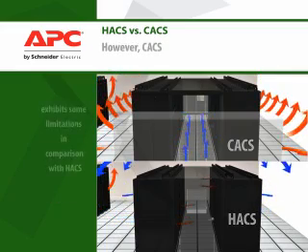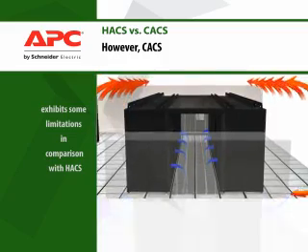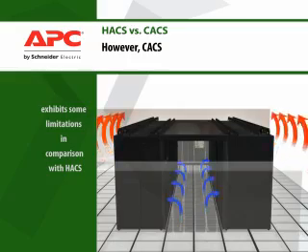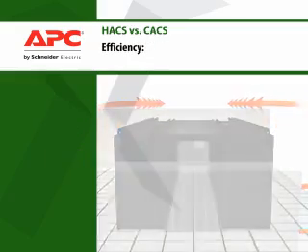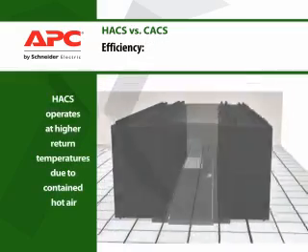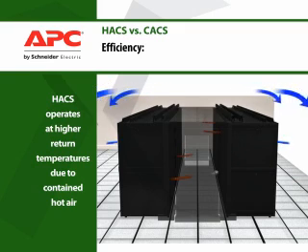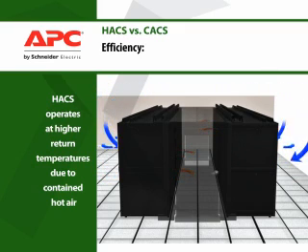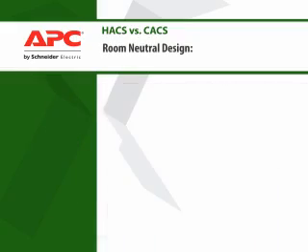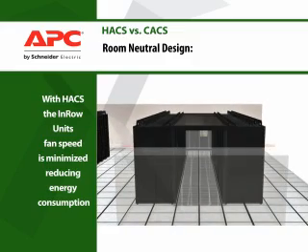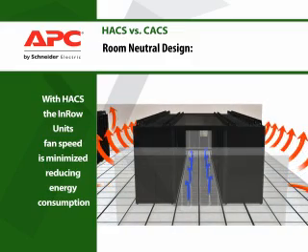While both the hot aisle and cold aisle systems help solve today's data center challenges, the cold aisle containment exhibits some limitations in comparison with the hot aisle system. With the hot air contained, the in-row cooling units are able to capture all of the heat from the IT equipment. Mixing from the room is also eliminated, which increases the return temperature, increasing cooling capacity and efficiency of the in-row cooling units. With mixing eliminated, the in-row cooling system's variable speed is minimized, further reducing energy consumption.